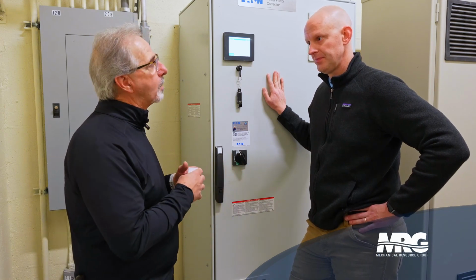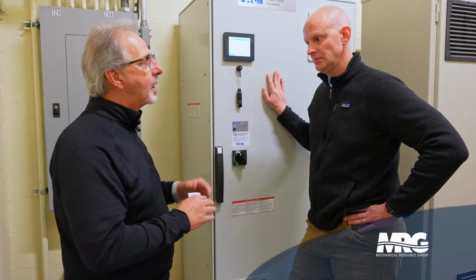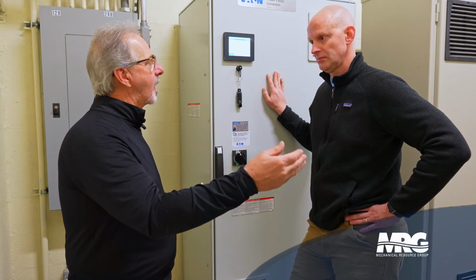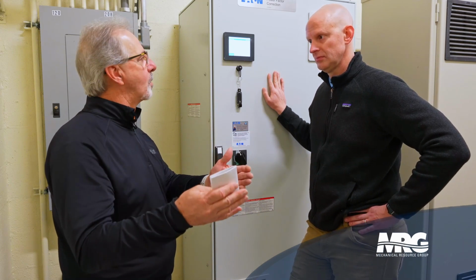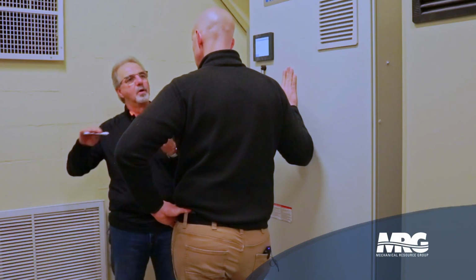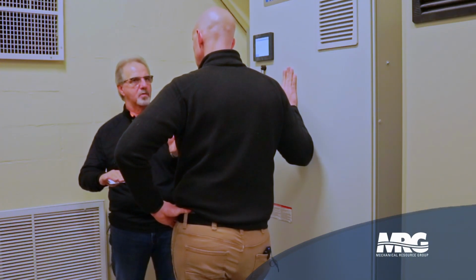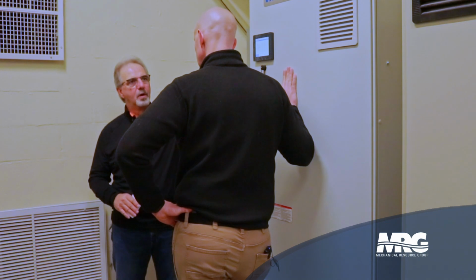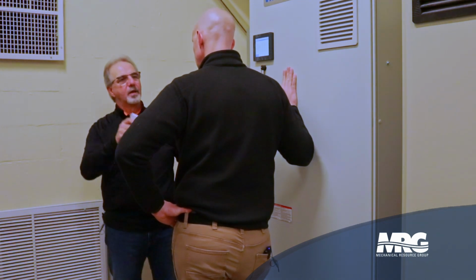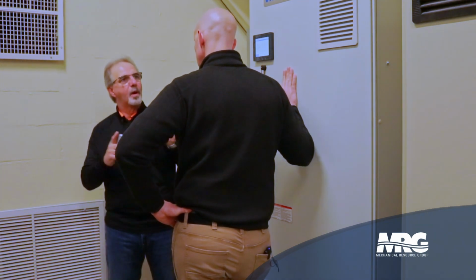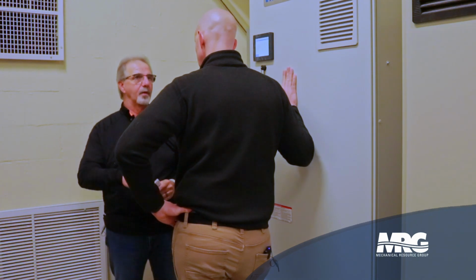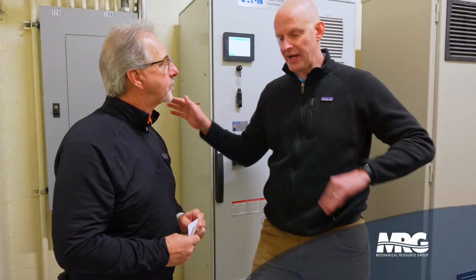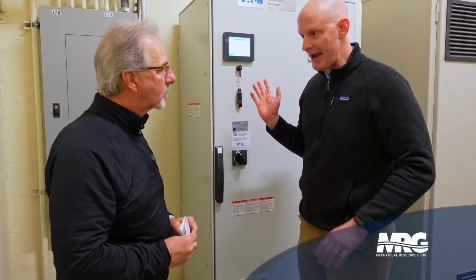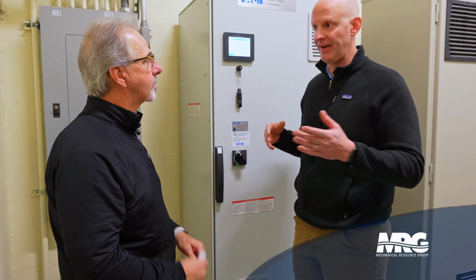Because what we want to do is make sure that we get equal run time. So we have an hour set on this drive. This drive will run for so many hours. It will shut down and move itself into that N3 position. The next pump will start. It moves into N1 position. The other pump is N2, and so on, so that we get equal runtime throughout the year. Yeah. So hey, we got a lot of redundancy. We got a lot of backup in case there is some type of failure.